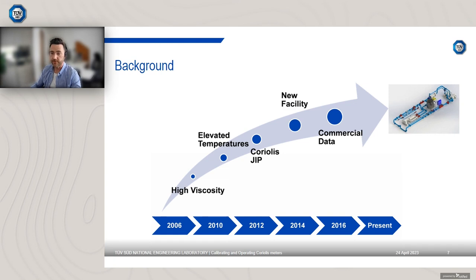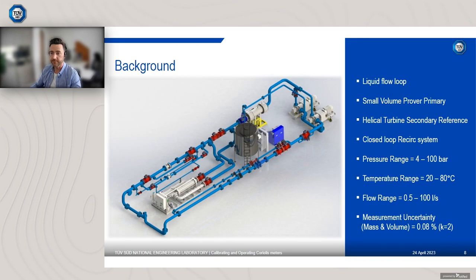So this is the elevated pressure and temperature facility, which you can see there. I have it here in a larger image, and I've got some detail along the right hand side. Now this is a liquid flow loop. It's a closed loop design. I don't think you can see my pointer, but in the centre of the screen you can see a storage tank. This is only used to fill and empty the line, maybe when we're doing a changeover of a test meter, for example, or maintenance. We fill the line. It's a closed loop facility, so it's fully purged of all air, filled completely with fluid, and then it's recirculated around.